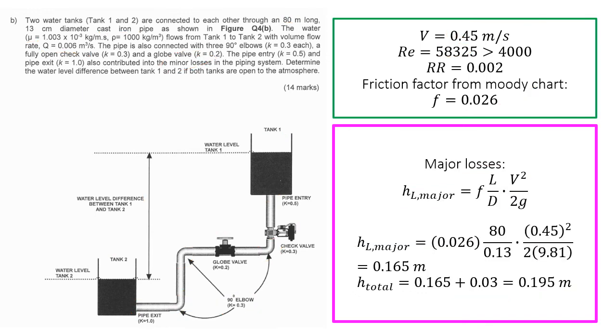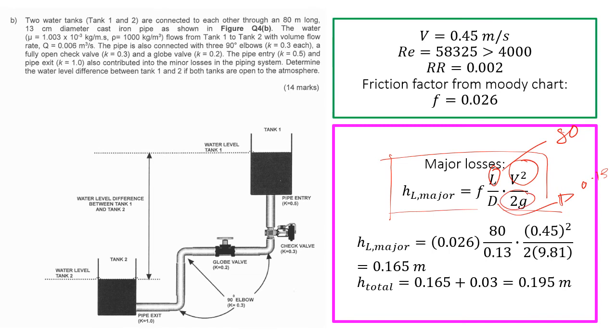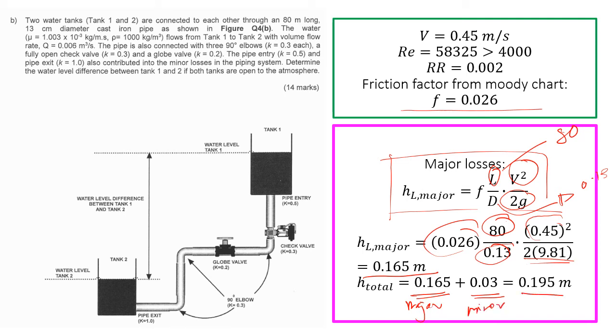For major losses, using the equation HL_major equals F times L over D times V² over 2G: F is 0.026, L is 80 meters, D is 0.13 meters, V is 0.45 m/s, and 2G is 2 times 9.81. Substituting gives 0.165 meters for the major losses. The total head losses is the sum of major and minor losses: 0.165 plus 0.03 equals 0.195 meters, which is the total losses in the piping system.